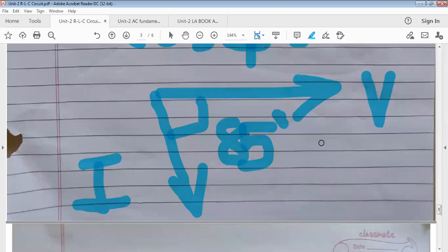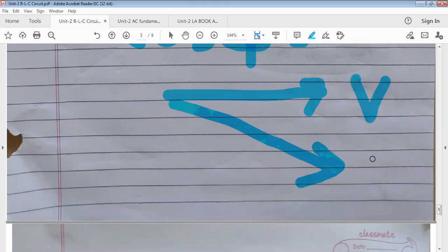So because the capacitor is supplying negative reactive volt ampere, XL and XC are opposite to each other, isn't it? Because of that, what happens? This angle phi gets minimized. Suppose it goes from 85 to 10 degrees. So this is the voltage and this is the current. The moment you switch on the capacitor bank, this angle gets reduced from 85 to, suppose, 10 degrees.